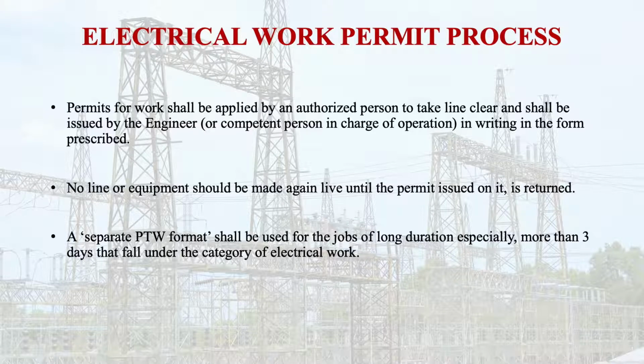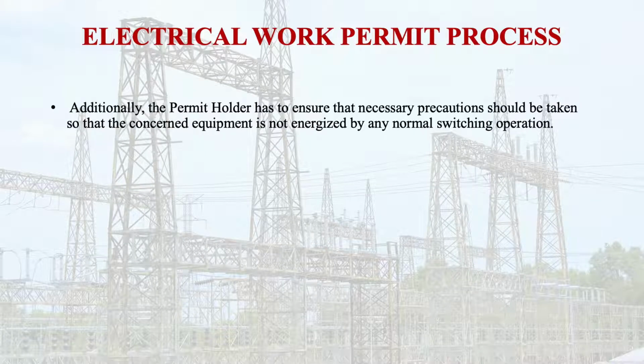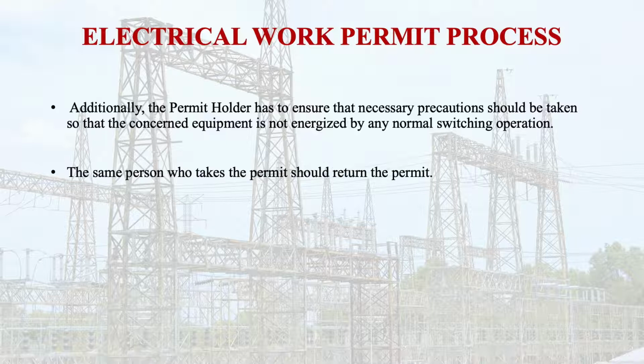A separate permit format shall be used for jobs of long duration, especially more than 3 days, that fall under the category of electrical work. Additionally, the permit holder has to ensure that necessary precautions are taken so that the concerned equipment is not energized by any normal switching operation. The same person who takes the permit should return the permit.